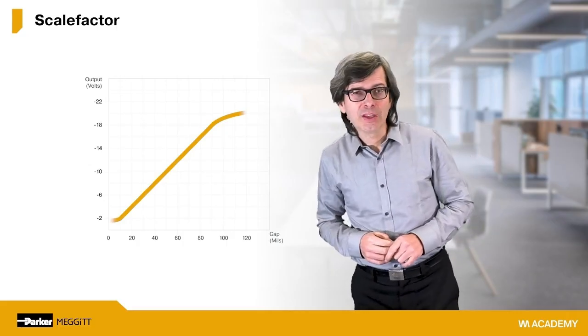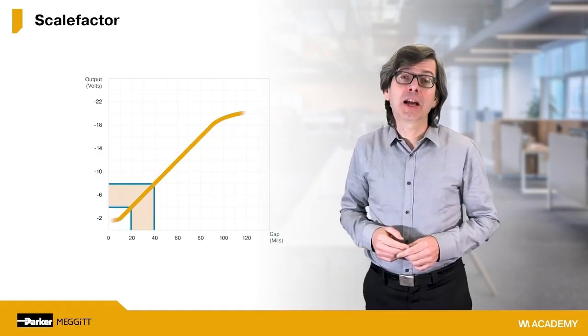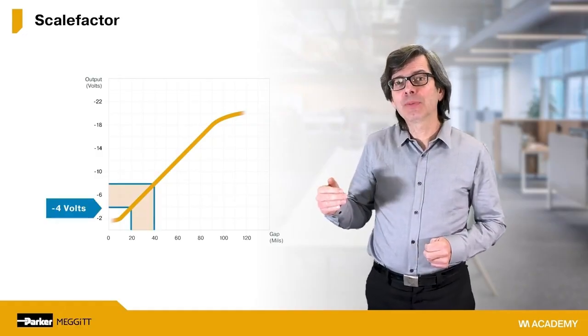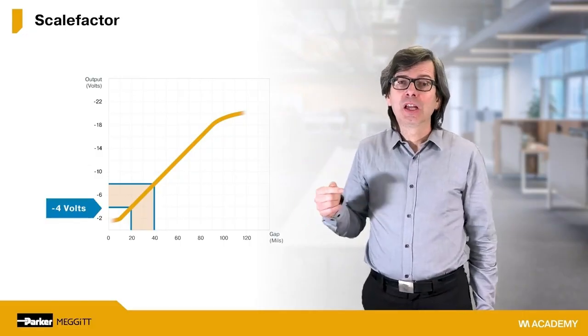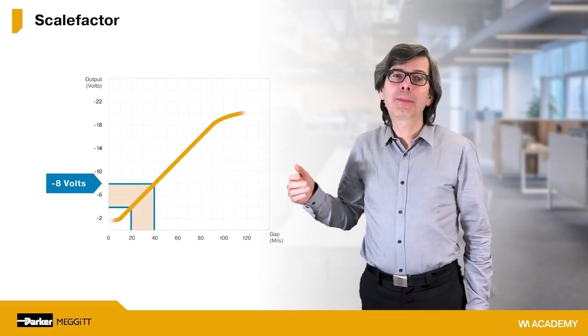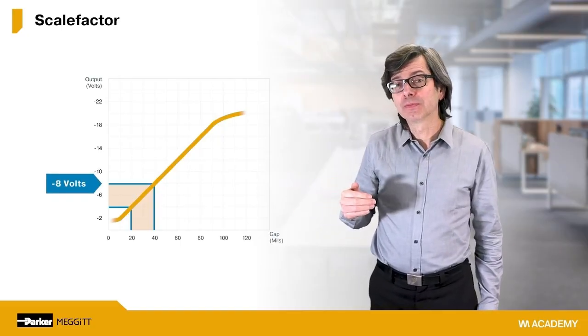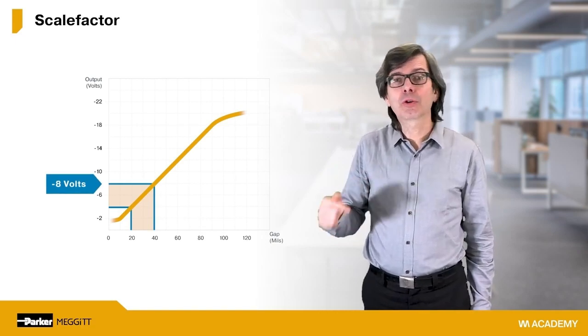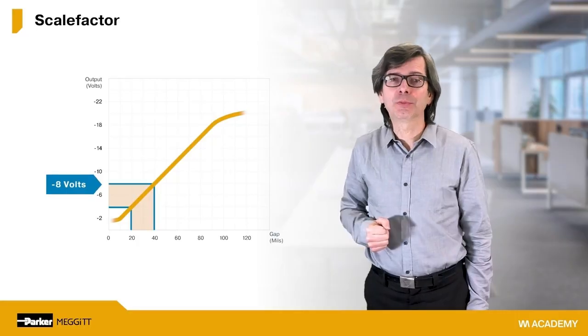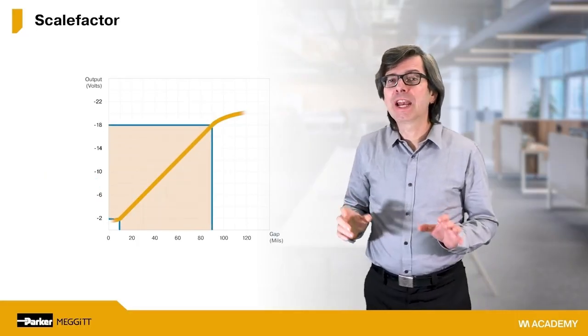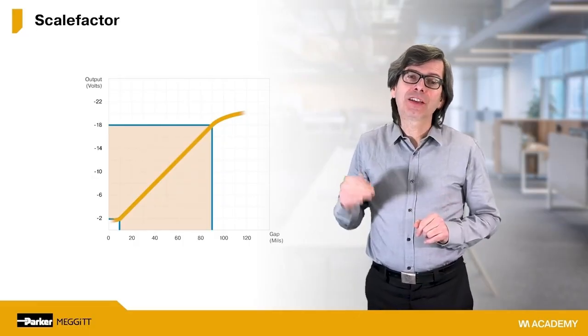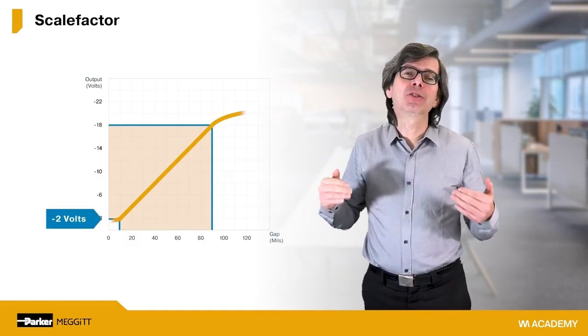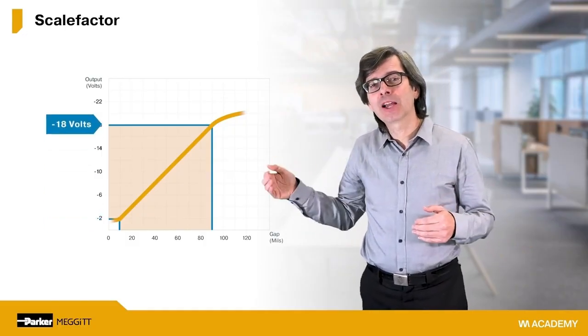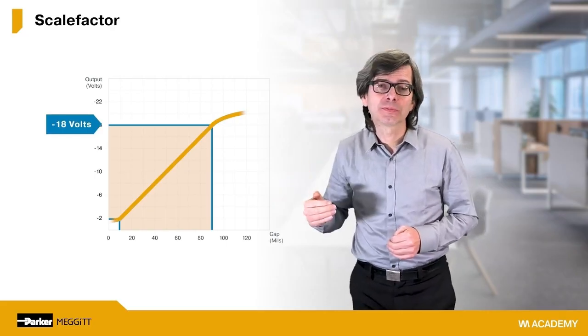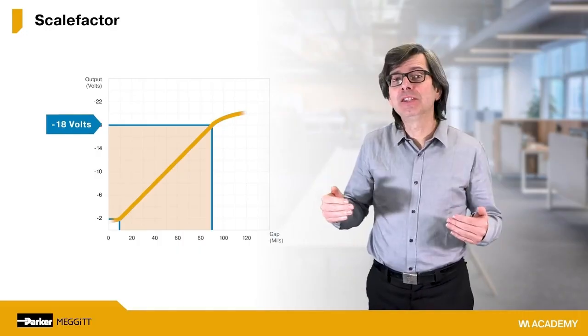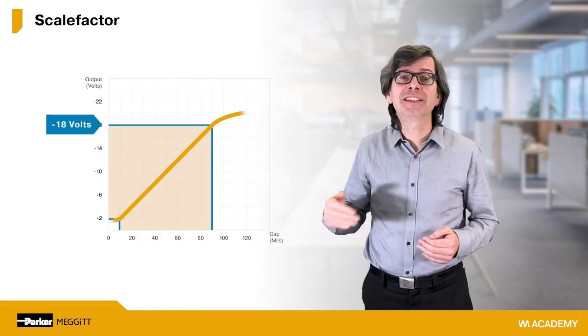Here we have shown a 20 mil change in gap. At 20 mils of absolute gap, the voltage is minus 4 volts. And at 40 mils of absolute gap, our voltage is minus 8 volts. The 20 mil change in gap, therefore, corresponds to a 4 volt change in output. Now we show an 80 mil change in gap. At 10 mils of absolute gap, the voltage is minus 2 volts. And at 90 mils of absolute gap, our voltage is minus 18 volts. An 80 mil change in gap, therefore, corresponds to a 16 volt change in output.